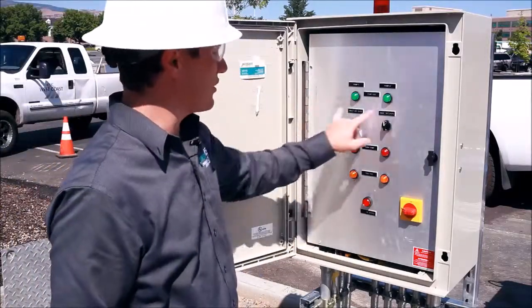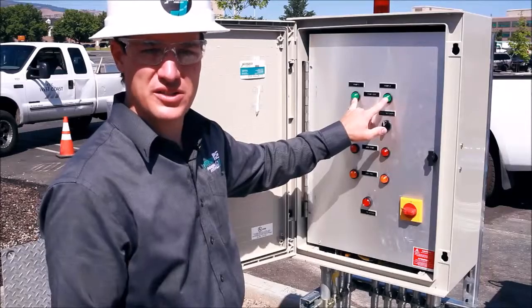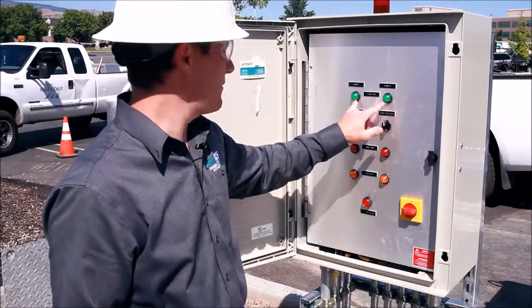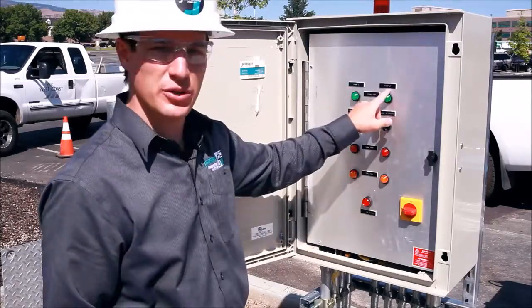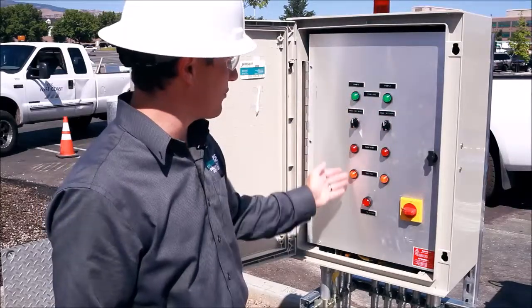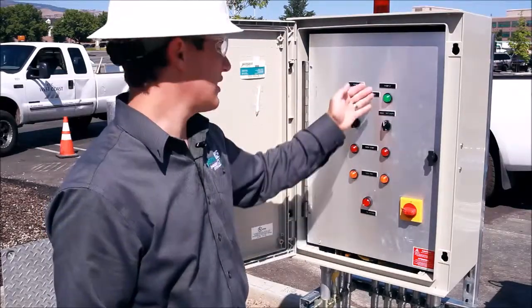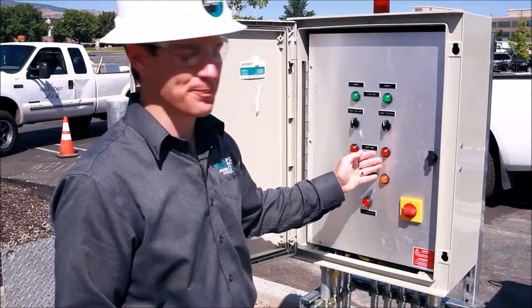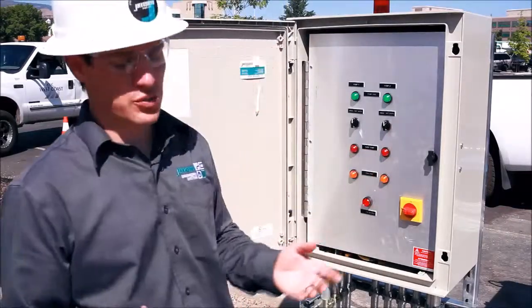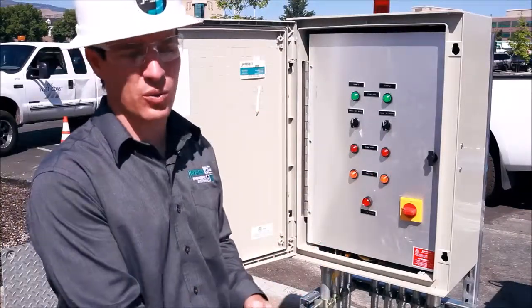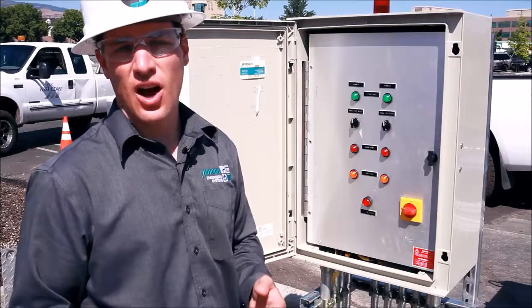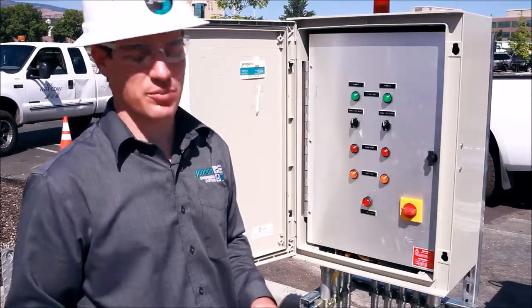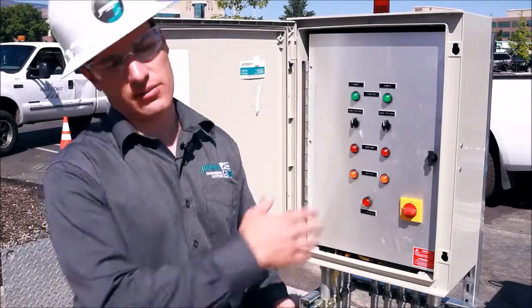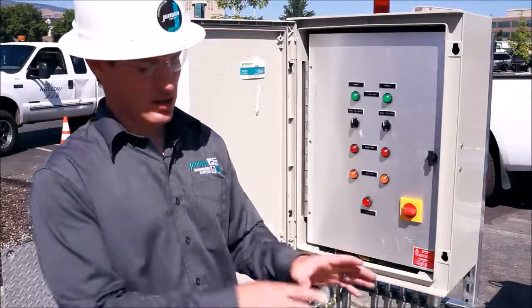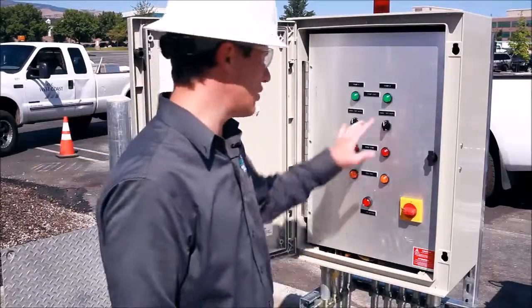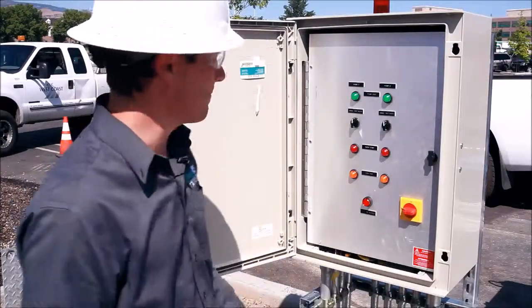As we move to the dead front, you'll notice we got some pump run lights. So these lights are telling us when the pumps are activated. You'll notice also pump 1, pump 2. Everything underneath pump 1 is associated with pump 1. Everything underneath pump 2 is associated with pump 2. To figure out which pump is actually which inside the wet well, you need to refer to the operations and maintenance manual supplied by Jensen Precast. And in that we designate east, west, north, south to let you know which pump's which, so that you know which ones these correspond to physically in the well.